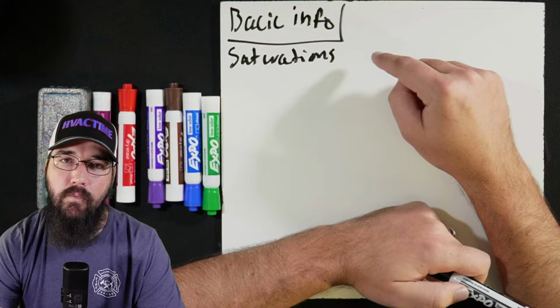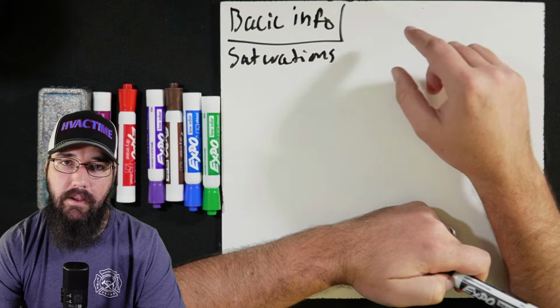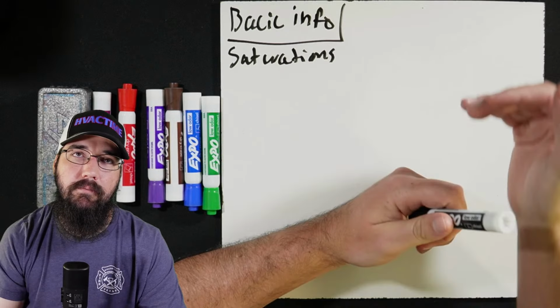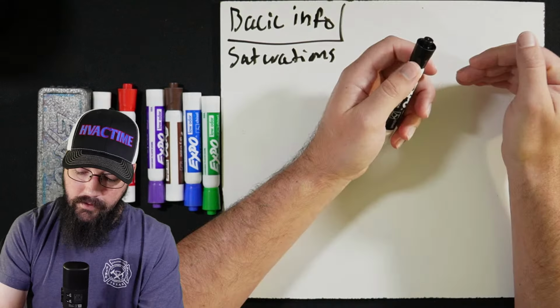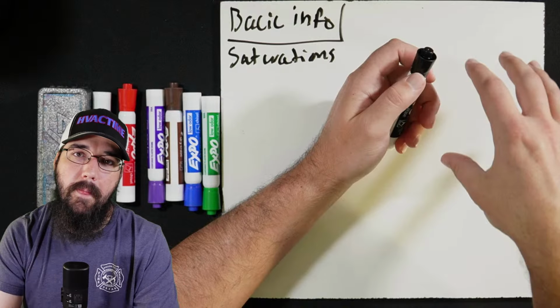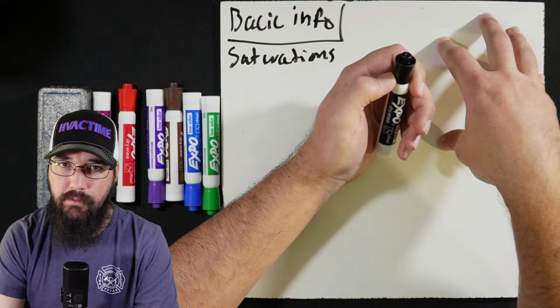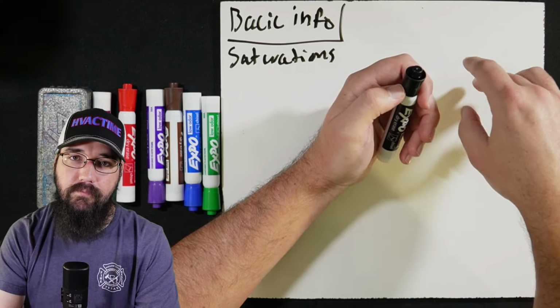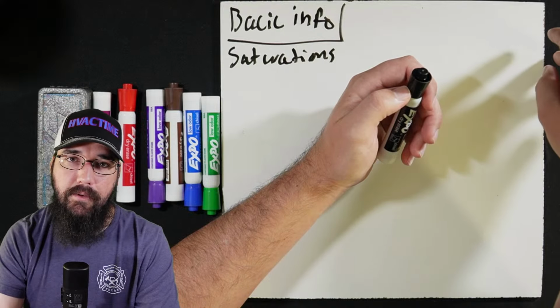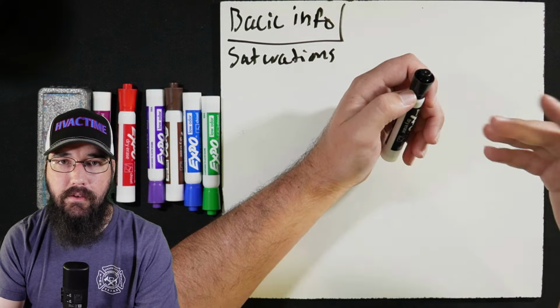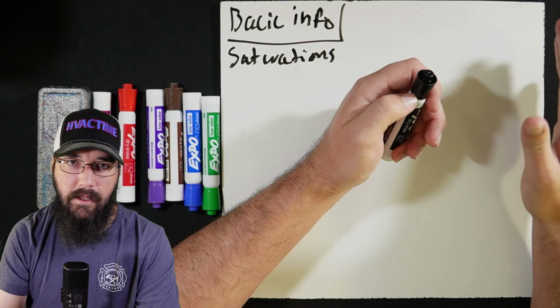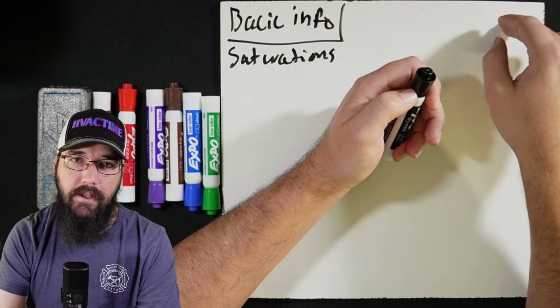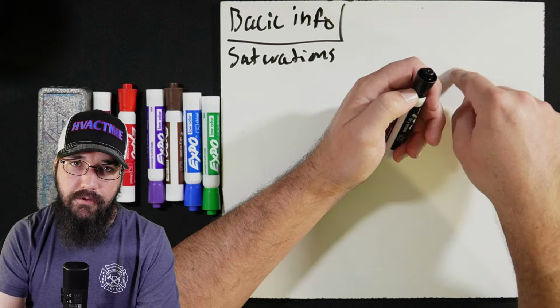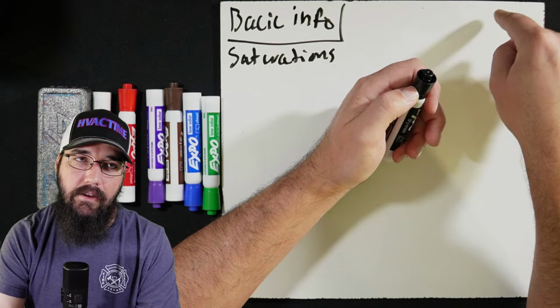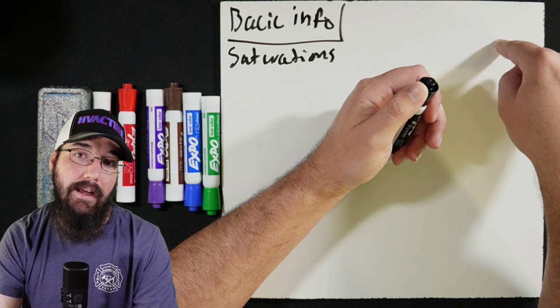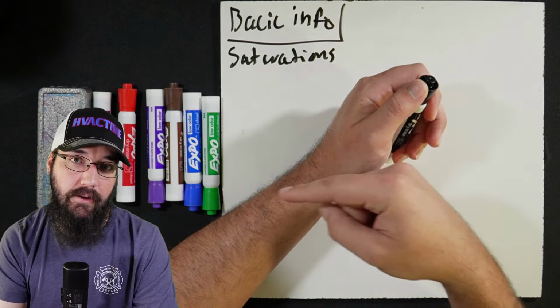Whereas a DX system, the refrigerant is directly in the load space. So, okay, let me scale back my terms here. I'm sorry. With an air handler, in a regular RTU or split system, the refrigerant is in the coil. That's absorbing heat directly from the load being the space. If we're in comfort cooling, specifically the most simple application here, we're taking heat out of the air. In a hydronic system, it is water that is taking the heat out of the air and then sending that heat to the chiller to then get rid of the heat somewhere else.